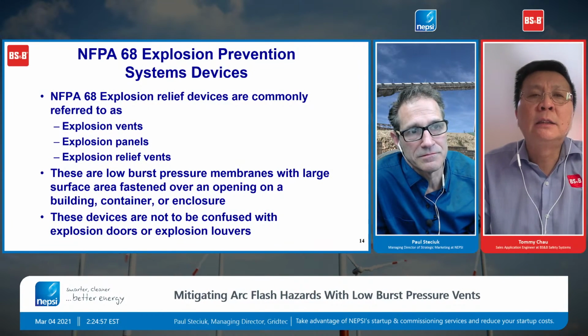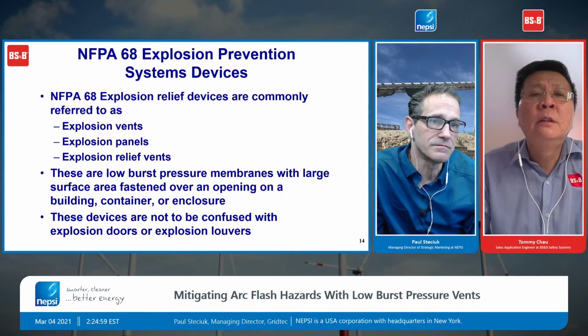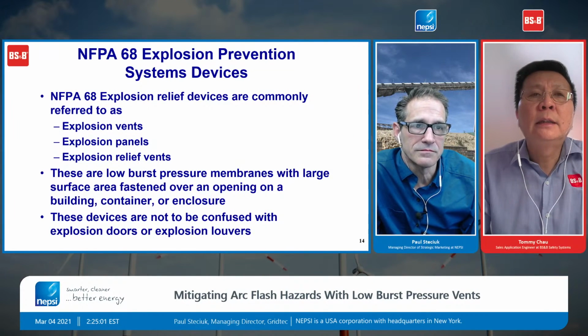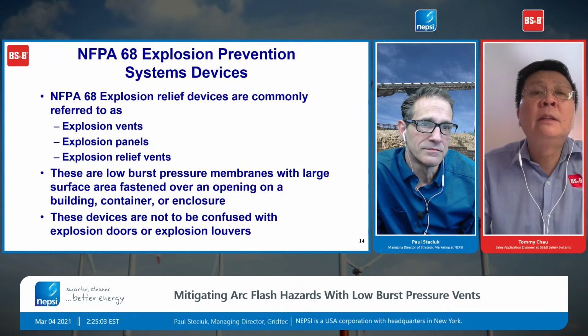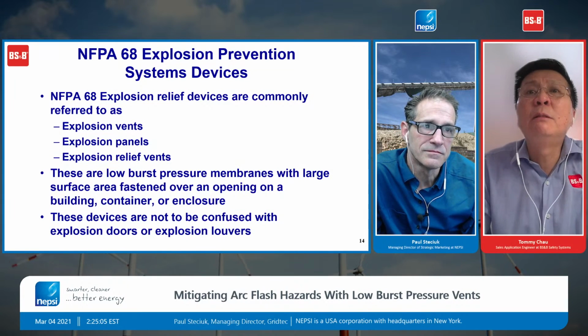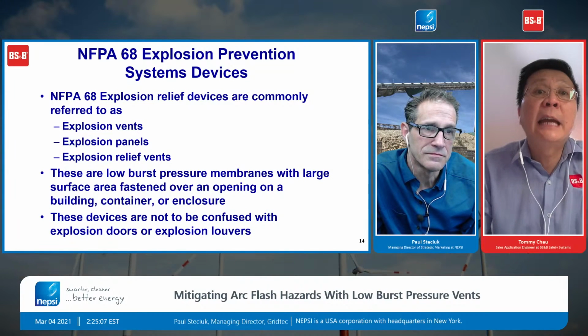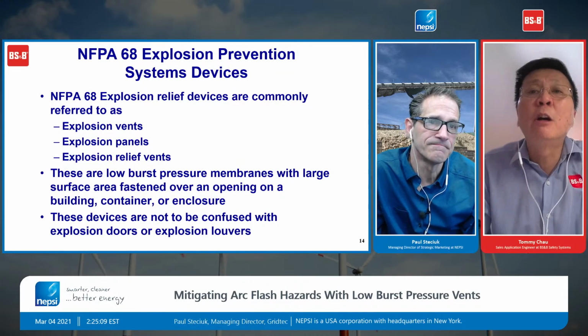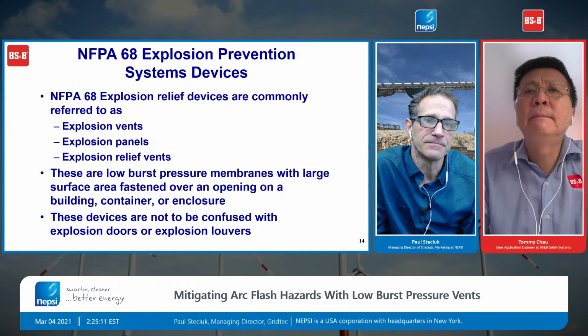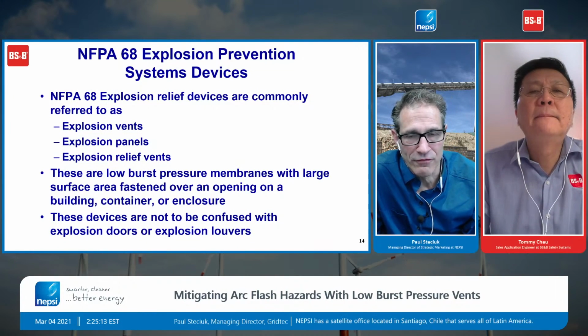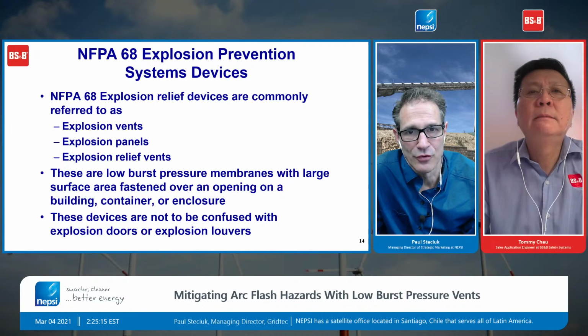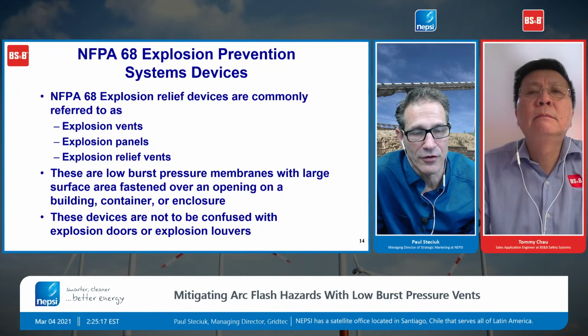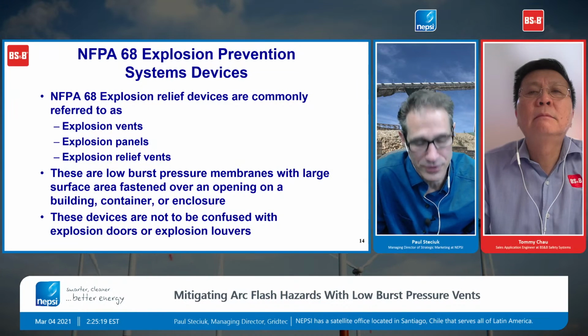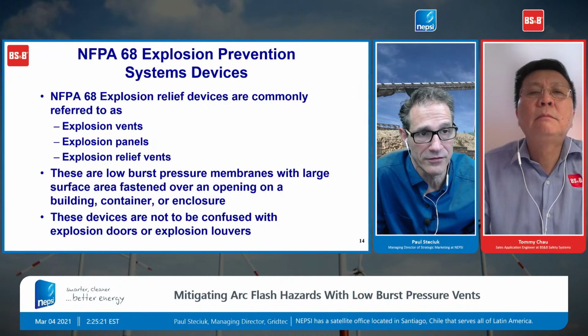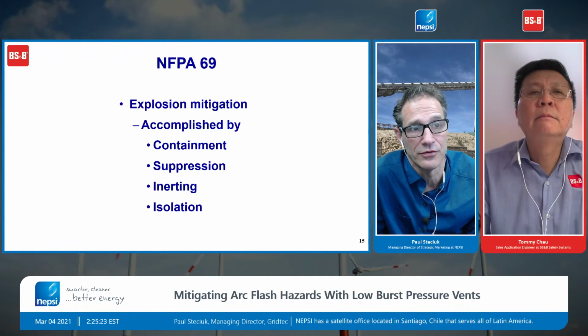The explosion door is a device that I believe you have to calibrate and do other tests on in the field to be able to reuse it. It is not made by us. Yes. Incidentally, when we have an arc flash event inside the enclosure, normally you are replacing a lot of other parts also. It's an explosion, so there are a lot of sensitive components that actually do fail in the end.